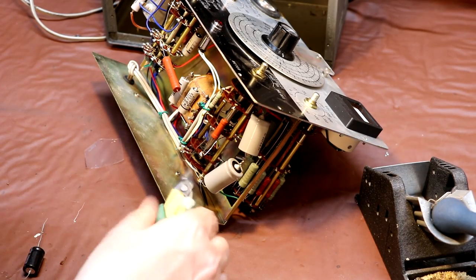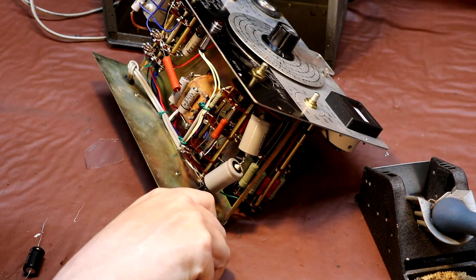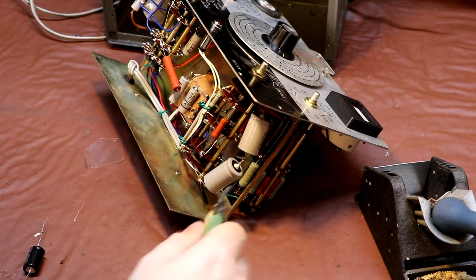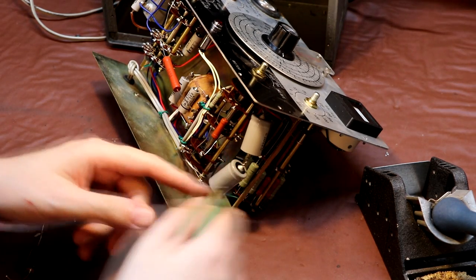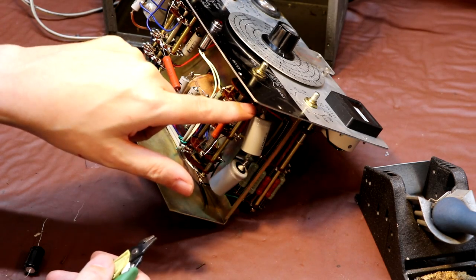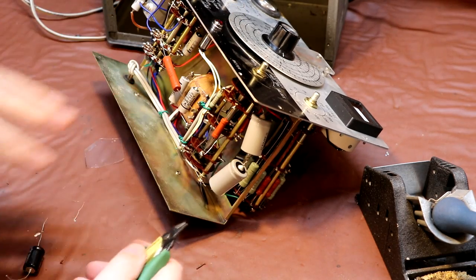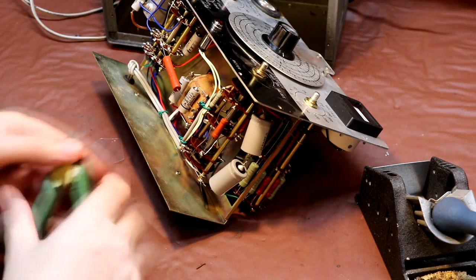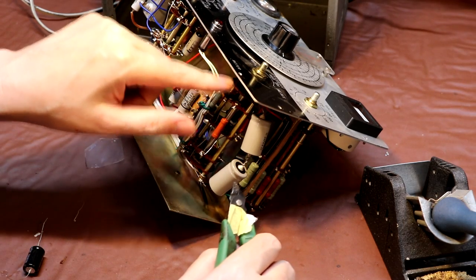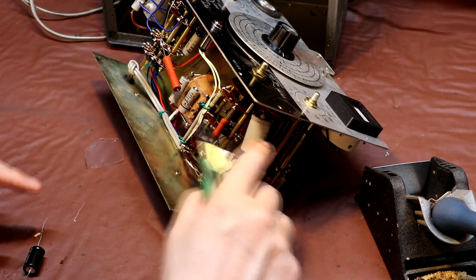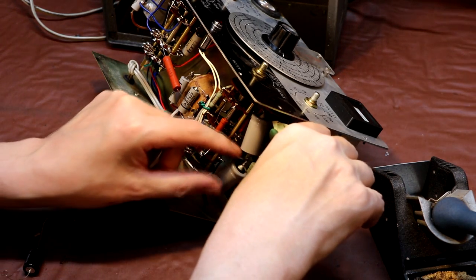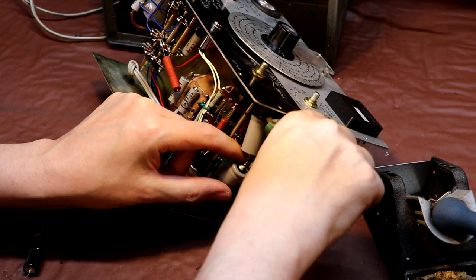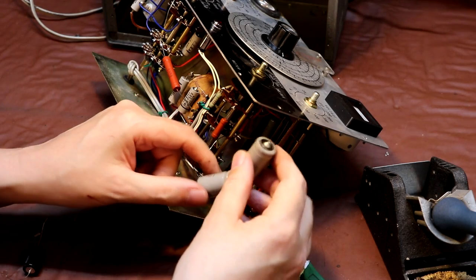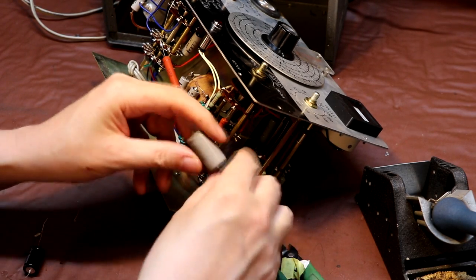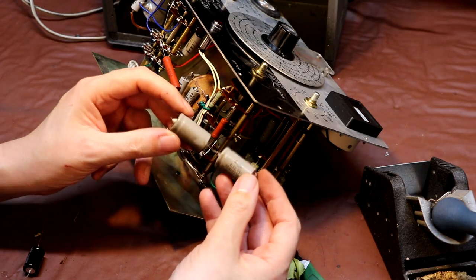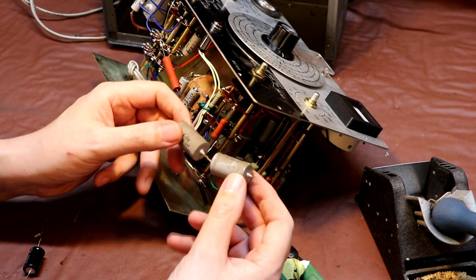Now the way that I'm going to remove and reinstall the new capacitors, I think I'm going to J-hook them in. The reason is that these capacitors go onto a selector switch on the terminal strip, and my experience is if you start messing around with the very thin wafers on these selector switches, you can very easily end up breaking the switch contacts off. I want to avoid that at all costs. That would be a very bad thing to happen, so I would rather be a little bit ugly and J-hook them in than risk damage on them.